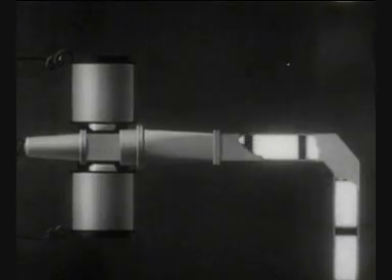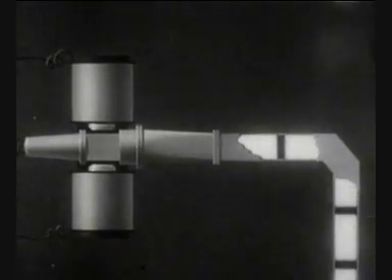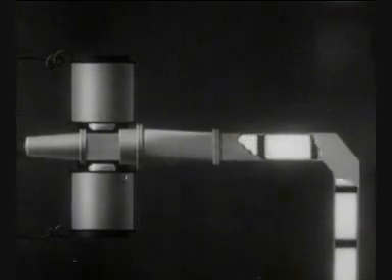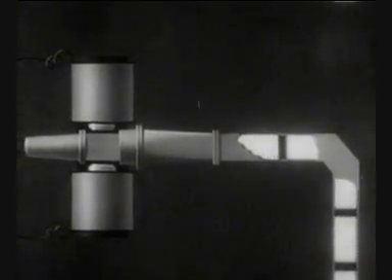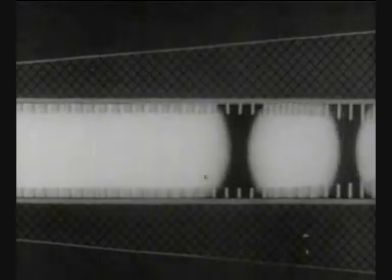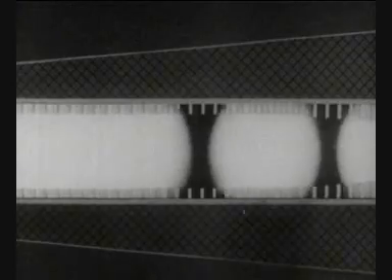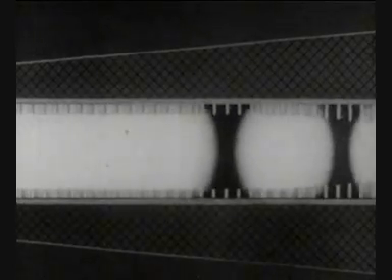The wave in the rectangular waveguide is traveling at a phase velocity of 140% c. On entering the cylindrical waveguide, corrugated by the iris plates, each field of the wave is slowed down to 40% c, which is the injection velocity of the electron. Then the changing guide dimensions in the iris plates permit the fields to accelerate.